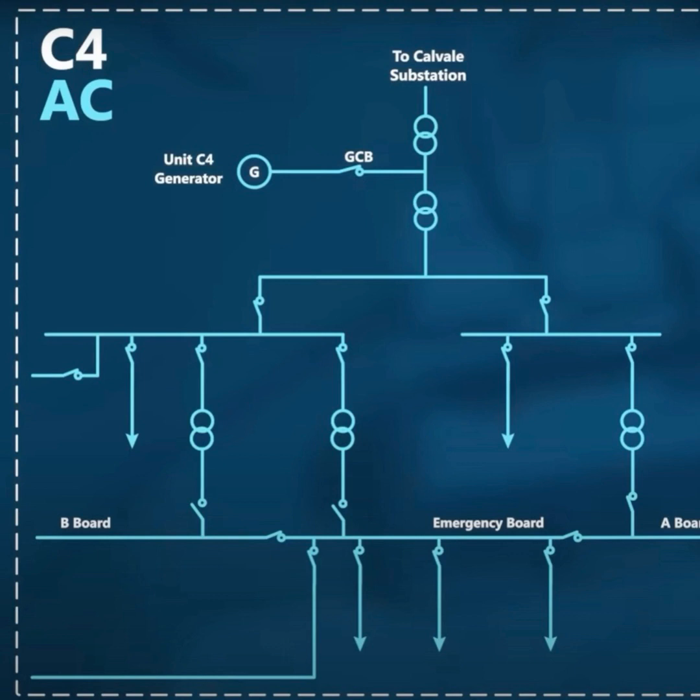As a result of that investigation, a design modification to the ACS controller that would have repaired the automatic changeover component damage was scheduled. However, those modifications had not yet been made. Specific details about what the damage was and what the modification was suggested are not available. However, it was at least a known issue.